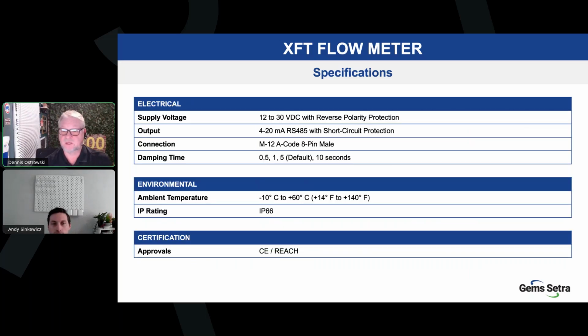Okay, some more specifications. The supply voltage that it supports is anywhere from 12 to 30 volts DC. The output, as we have said before, is 4 to 20 milliamp, but you've also got the Modbus via RS-485. The connection on the device is a male 8-pin M12, and I've already gone over the damping times that are available. You've got a 1/2 second, 1 second, 5 seconds, which is the default, or 10 seconds.